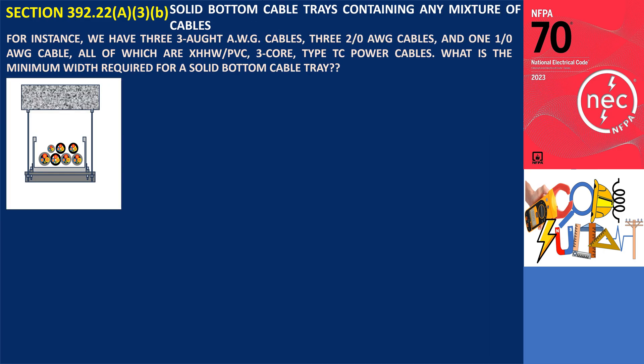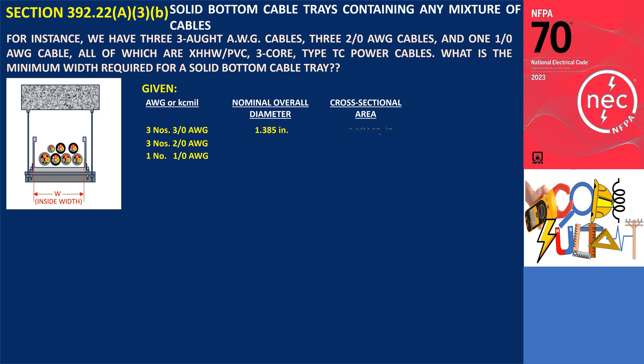Let's have an example. We have three 3-aught AWG cables, three 2-aught AWG cables, and one 1-aught AWG cable, all of which are XHHW, PVC, 3-core, type TC power cables. What is the minimum width required for a solid-bottom cable tray? The overall cross-sectional area for the 3-aught AWG cables is 4.42 square inches, for the 2-aught AWG cables is 3.85 square inches, and for the 1-aught AWG cable is 1.105 square inches.